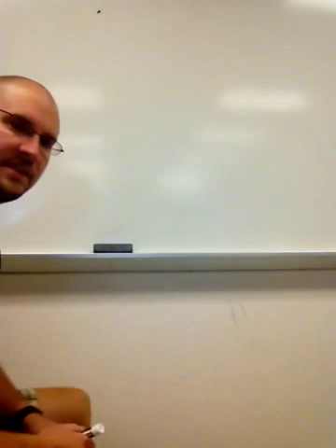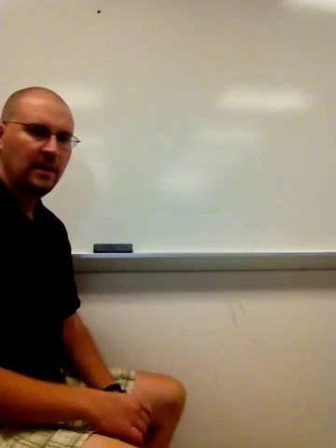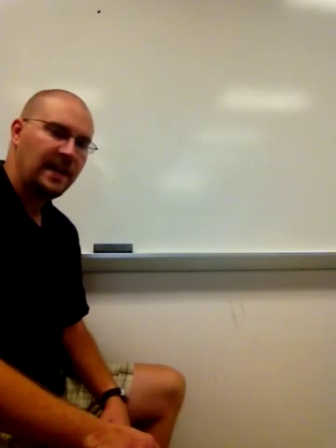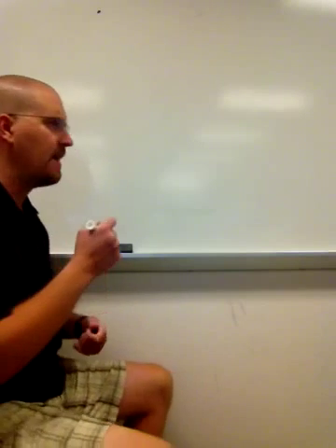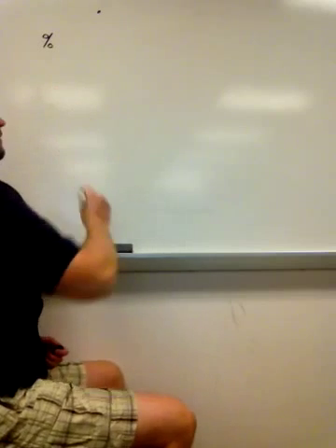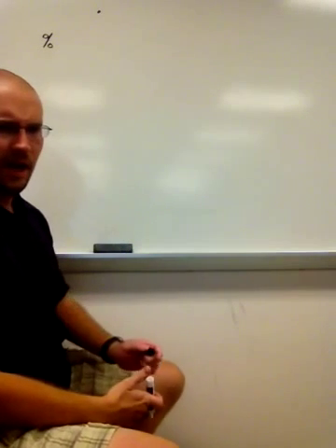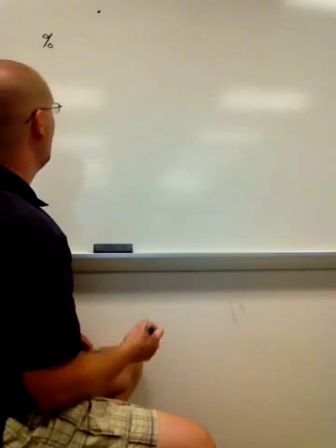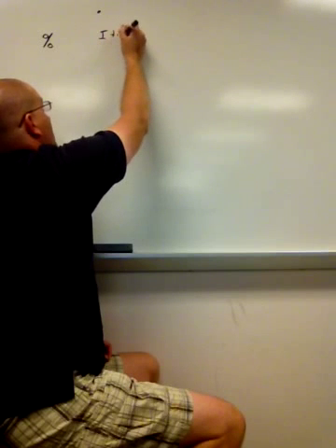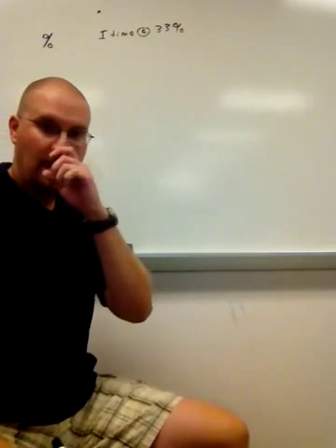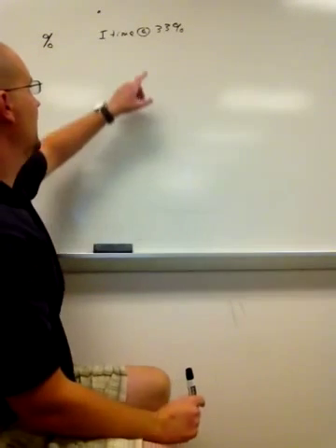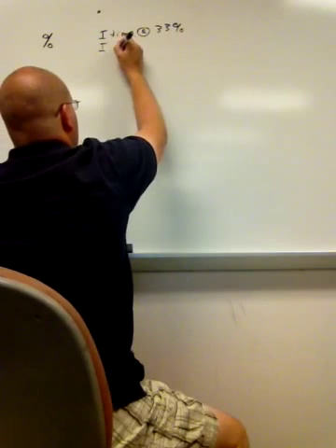The question comes down to something like this. Occasionally we see this with ventilator management. You'll certainly see this with the high frequency oscillatory ventilators, the 3100A and B series of ventilators, where when we are setting our inspiratory time, we'll set a percentage instead of a defined time. Let's say that we set our I time at 33%. Then there might be a question: if my I time is set at 33%, what is my I to E ratio?